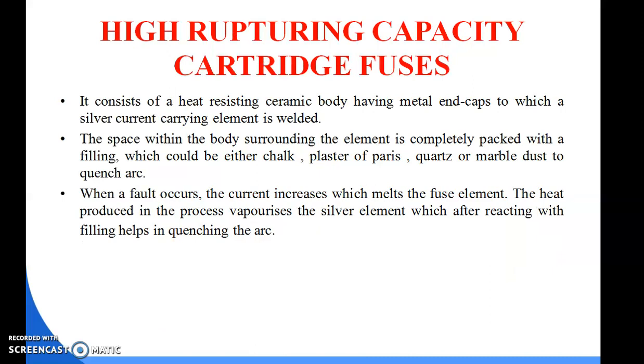High rupturing capacity cartridge fuse is another type of fuse. It consists of a heat resisting ceramic body having a metal end cap to which a silver current carrying element is welded. The space within the body surrounding the element is completely packed with a filling, which could be chalk, plaster of Paris, quartz, marble dust, or diatomaceous earth.